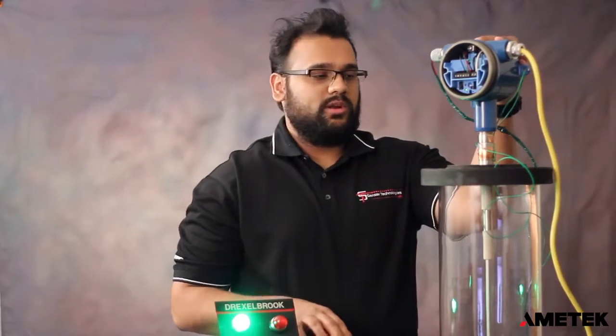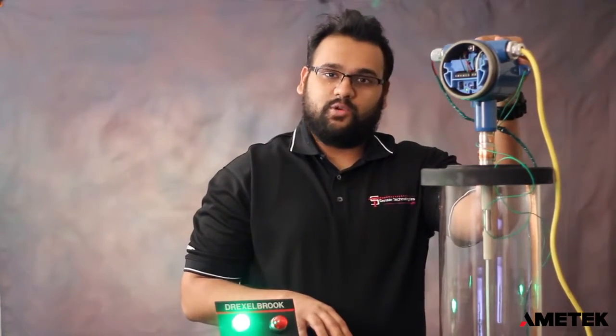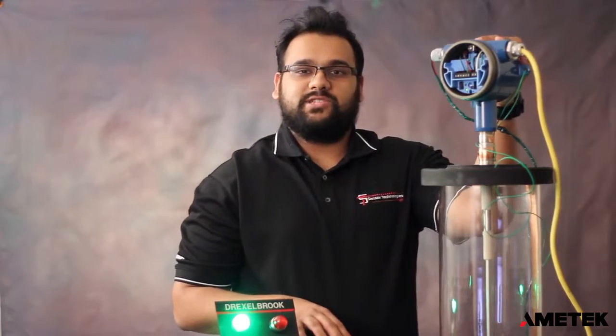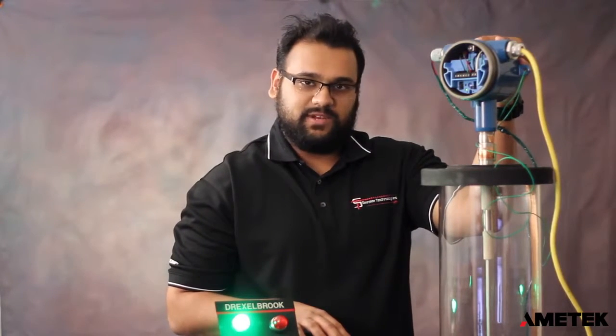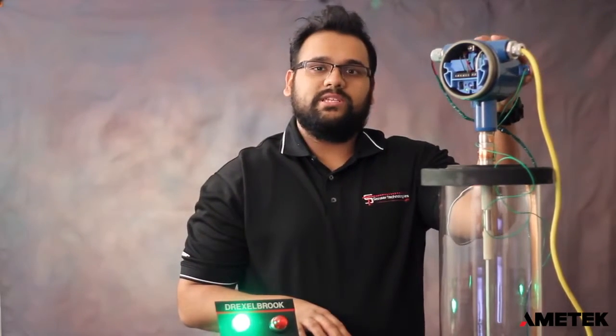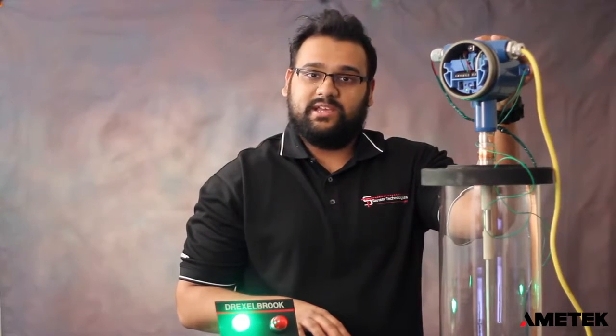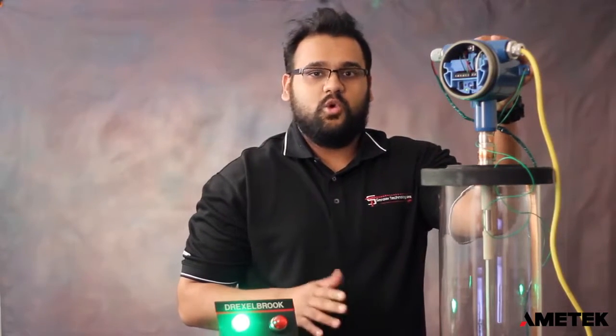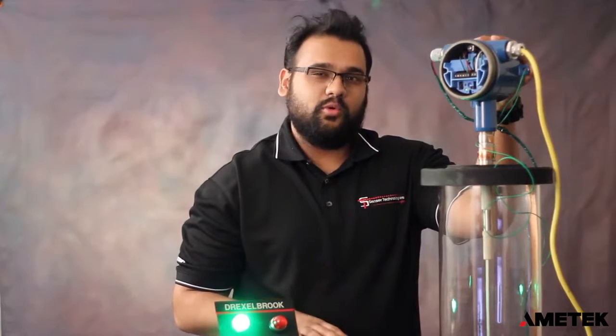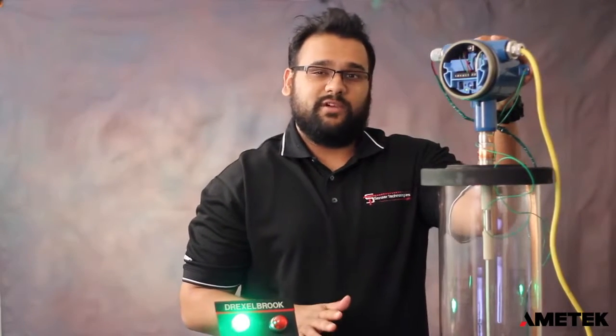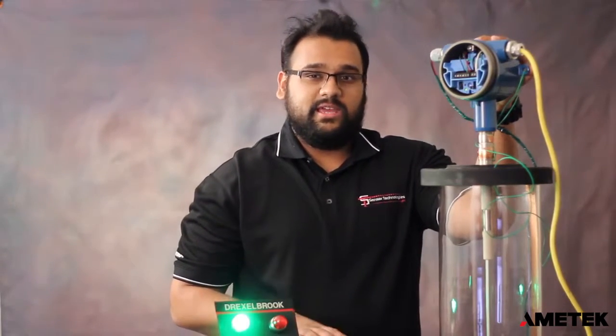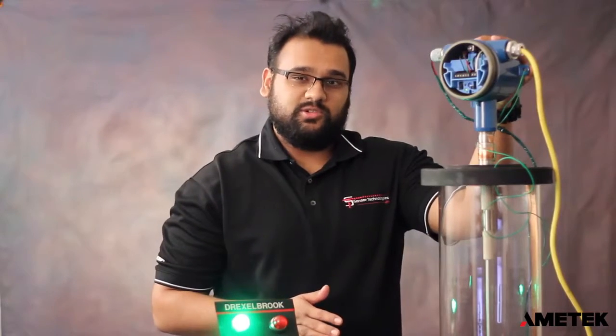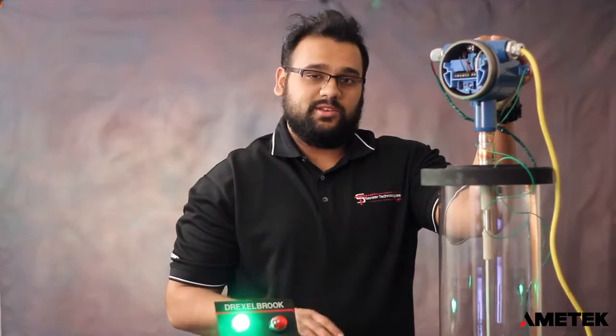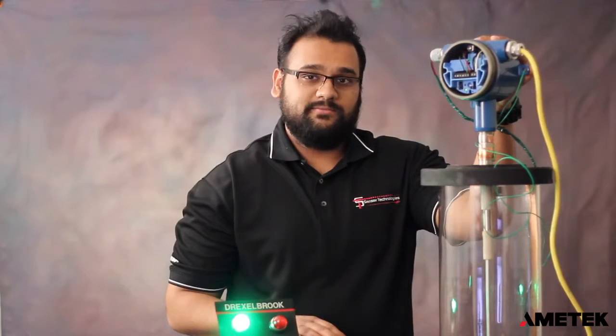fail-safe. You want to set your mode to either mode 7 or mode 8. Mode 7 being standard sensitivity, mode 8 being high sensitivity. This particular unit is already set to mode 8 for high sensitivity because today we're going to be measuring sawdust, which has a low dielectric of around 1.3 and a bulk density of roughly 13 pounds per cubic foot. If you're not sure how to change the calibration modes on your point, be sure to check your user's manual or check out our tutorial on YouTube.